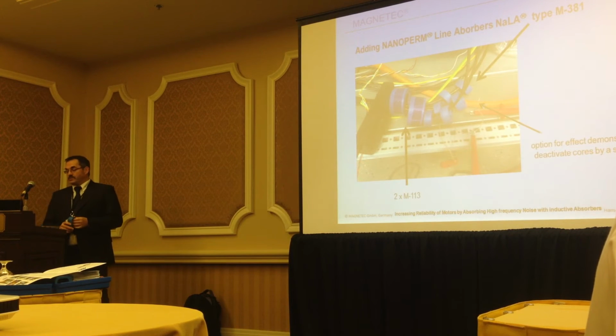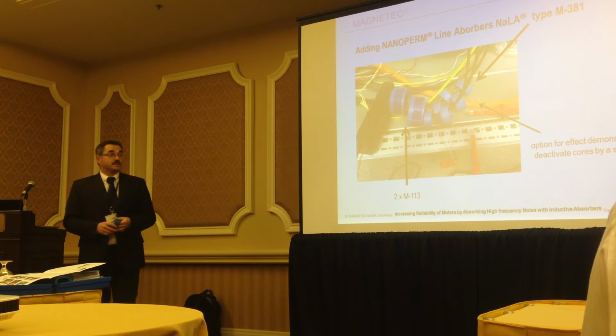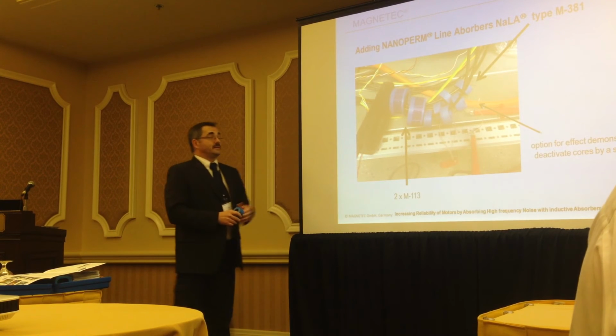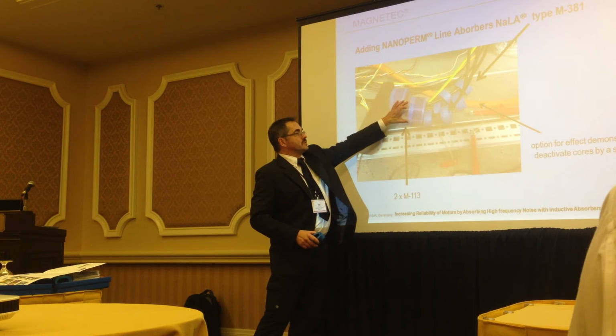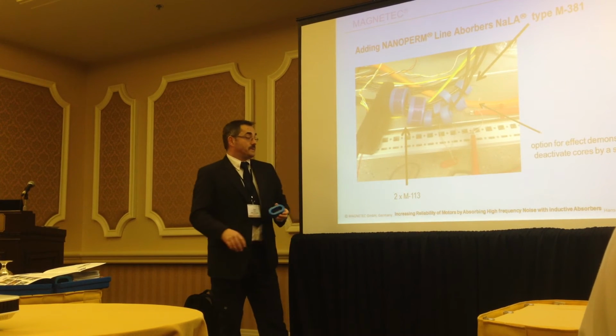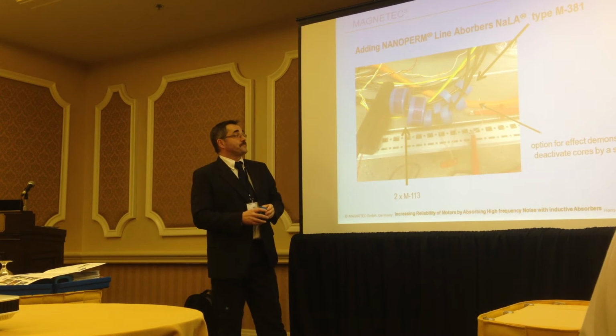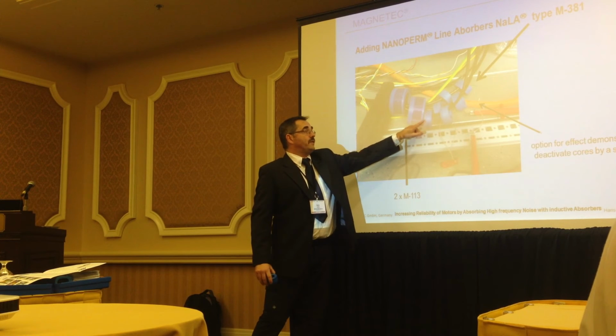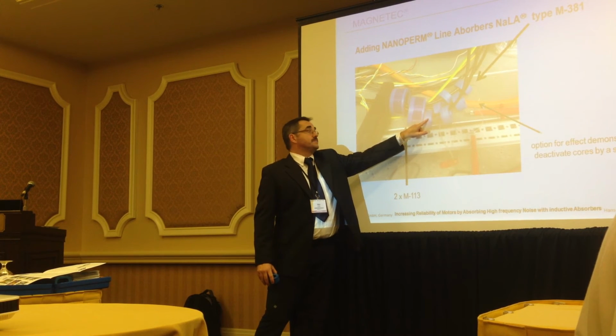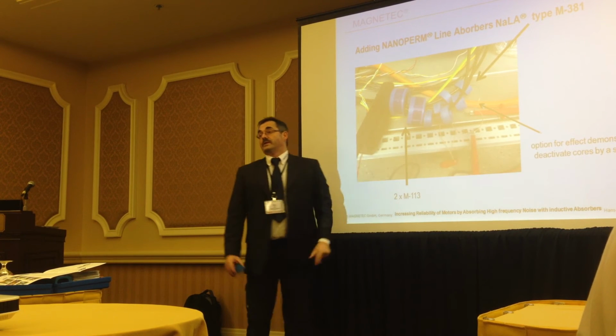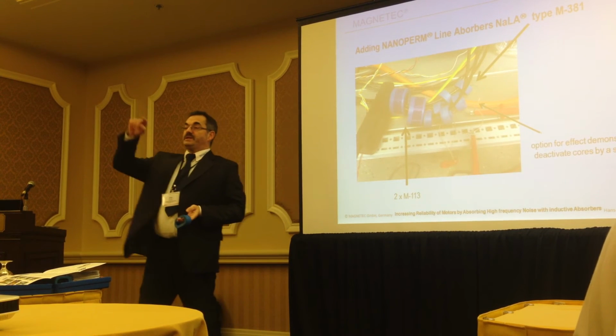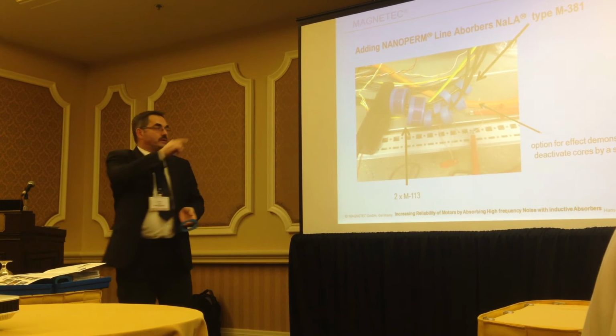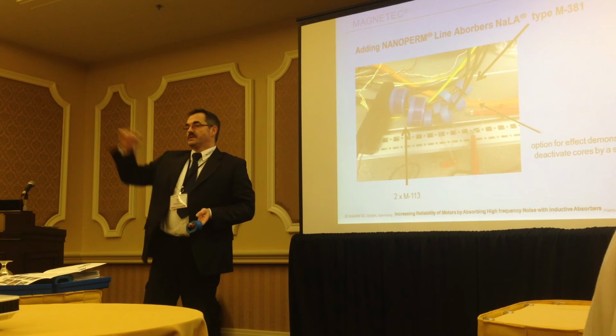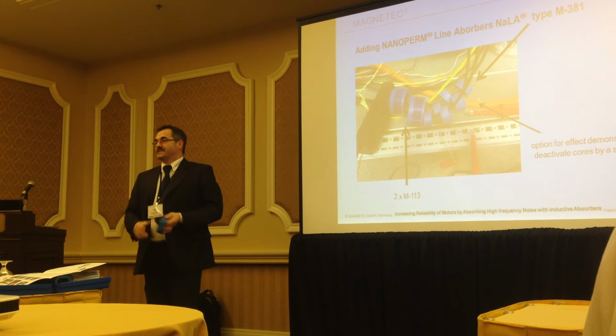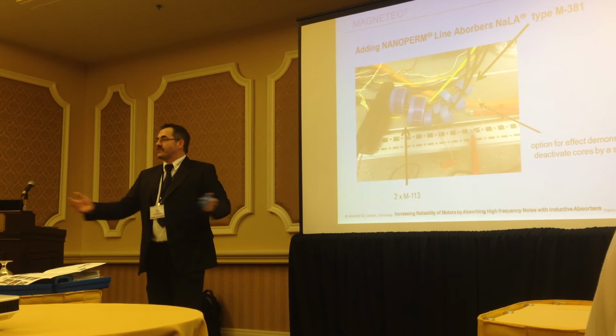Now we're coming to a mixture between common mode and differential mode - I know it's a little complicated, but it's real life. These are the common mode cores, placed over all 3 cables of the application, in this 50 kilowatt example. One of the new things we found is we can combine the common mode cores with very high permeable NANOPERM line absorber cores, one on each line. What they do is smooth the ringing that normally occurs when the IGBT switches. And what I learned after half a bottle of red wine: the source of common mode is differential mode.